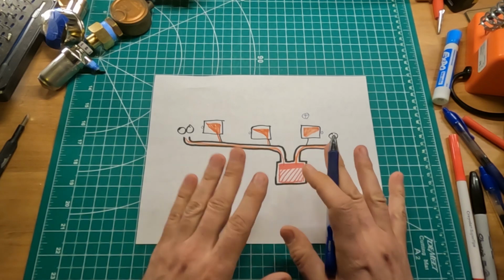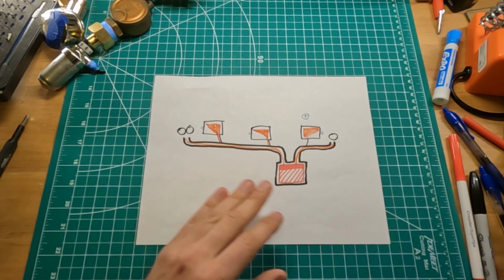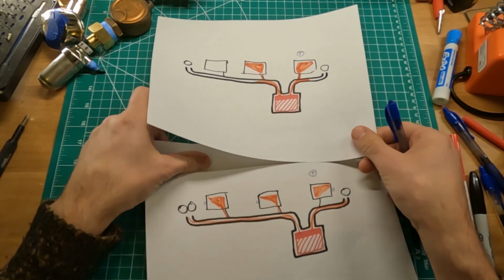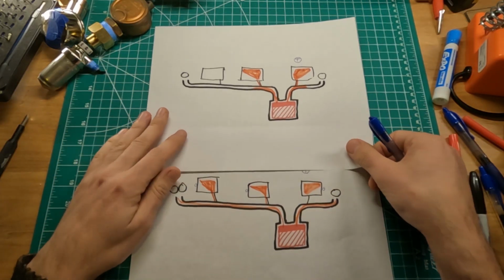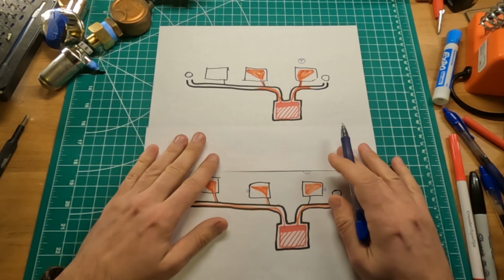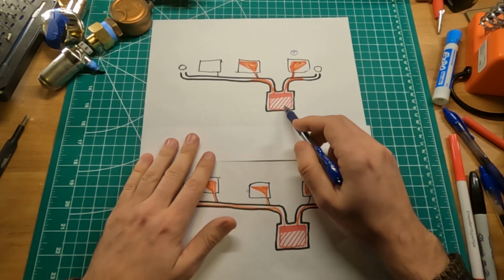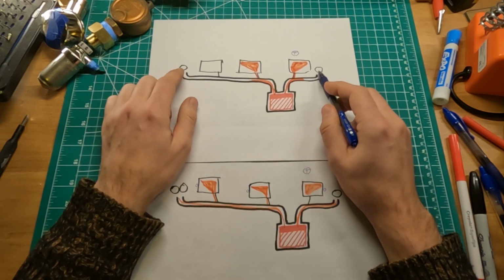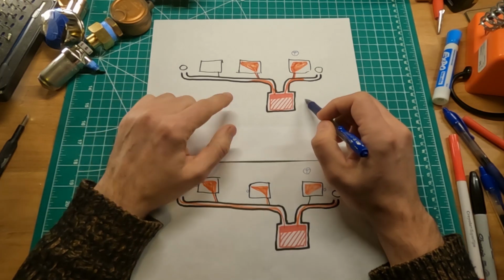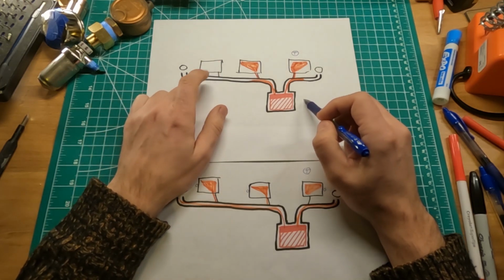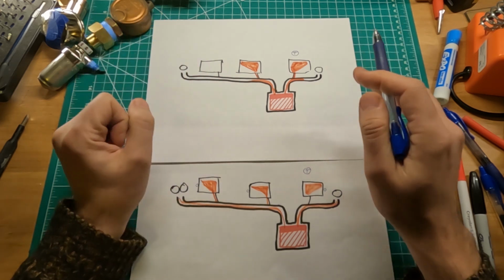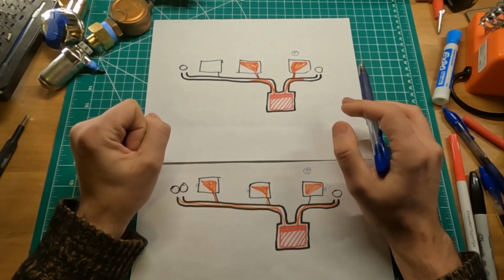So in that sense, let's say, again, to use a real world scenario, it does work maybe like this. Yeah, I used to have this scenario in my own house at first. I actually have quite decent venting, as in two large vents at the ends of the mains on both legs, the short one and the long one. But the long one had a few, quite frankly, radiators at the end of it that were always lukewarm. They never heated up too well.